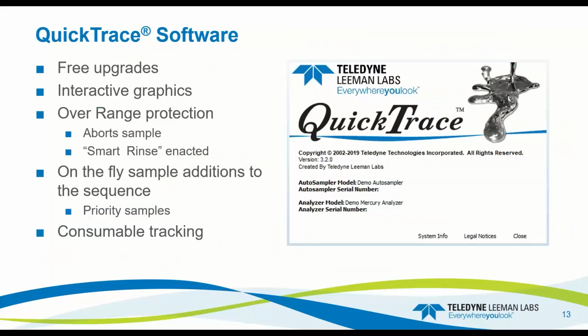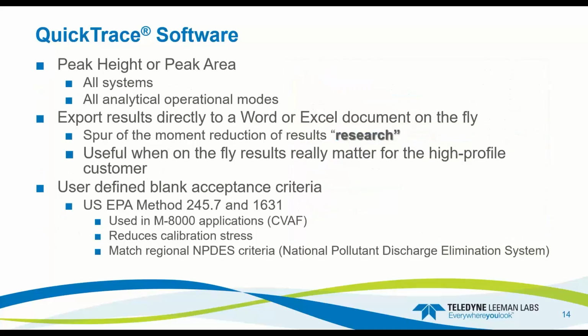Quick Trace software. So now that we know how to set the tubing, how to set it up, and how to adjust the flows, we'll quickly talk about what we do in the software. So we have free upgrades, interactive graphics, and that's key, overrange protection on the fly, sample additions, and consumable tracking. We have peak height or peak area in all systems and all analytical modes, and that really helps you dial in the system for how you want to run it.